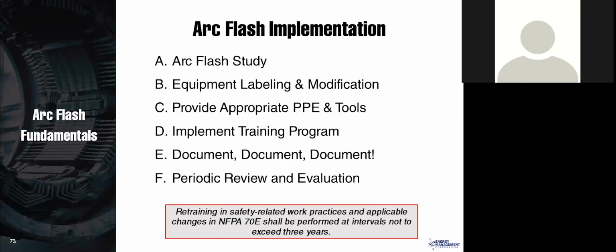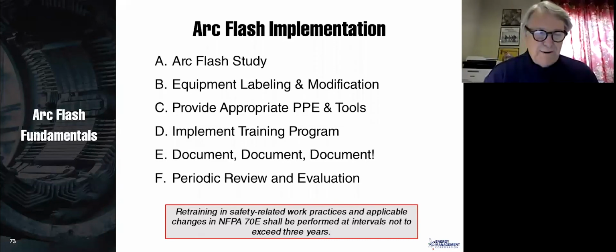Great. Next question. Does molded case breaker have to be injection tested, or does the exercise yearly count as still suitable? According to that paragraph I showed you in the code, it needs to be injection tested, but remember that we're only talking about injection testing for breakers that have arc flash mitigation on them. So there isn't a requirement during the startup that you test all your breakers. You only have to test the ones that have arc flash mitigation on them, such as an arm switch. With other breakers, there isn't that requirement for injection testing.